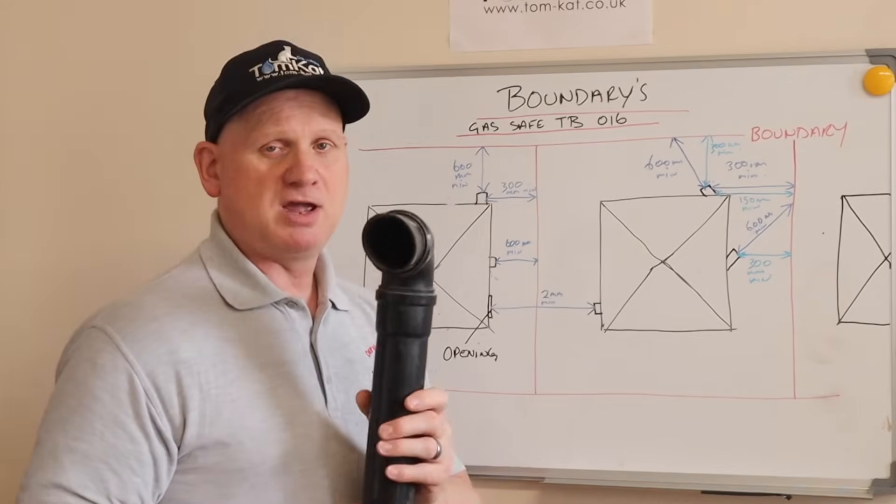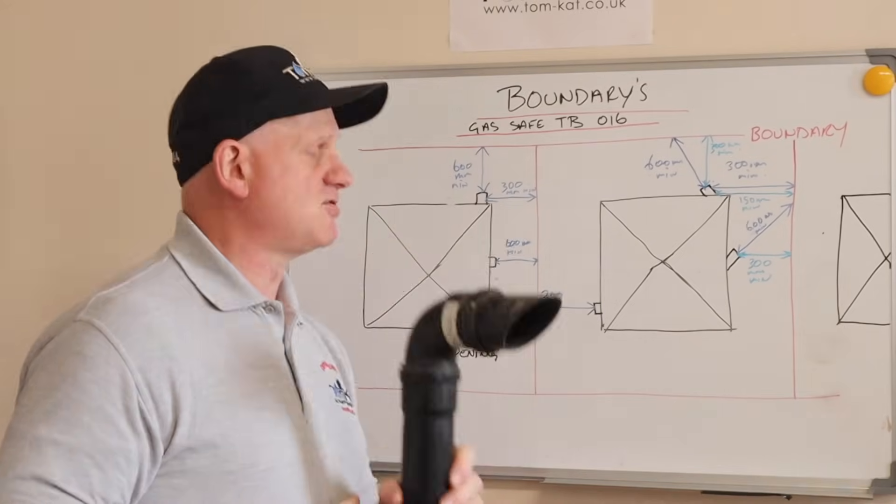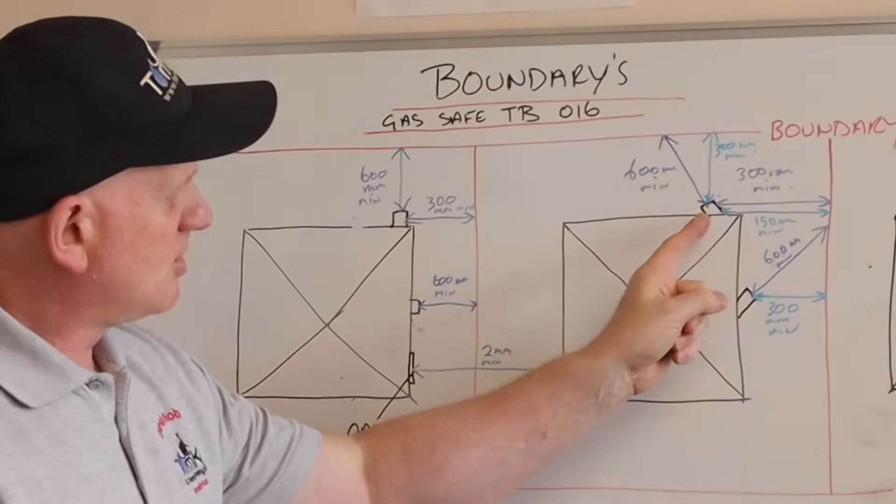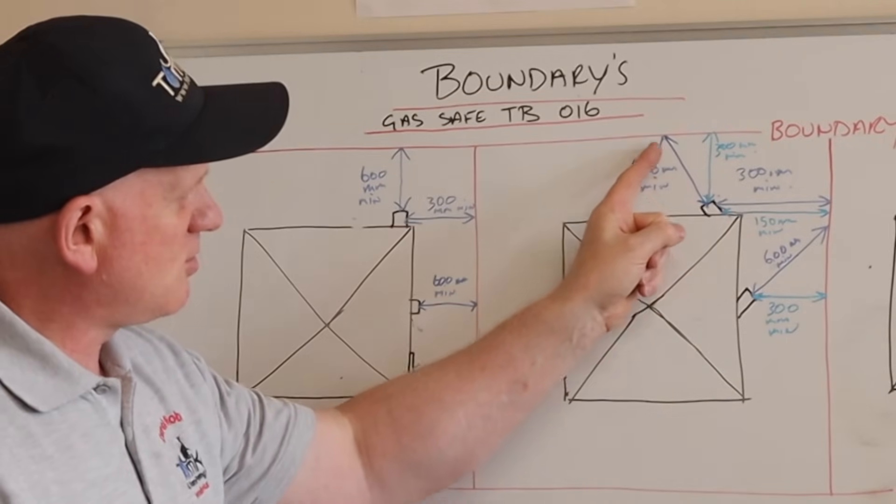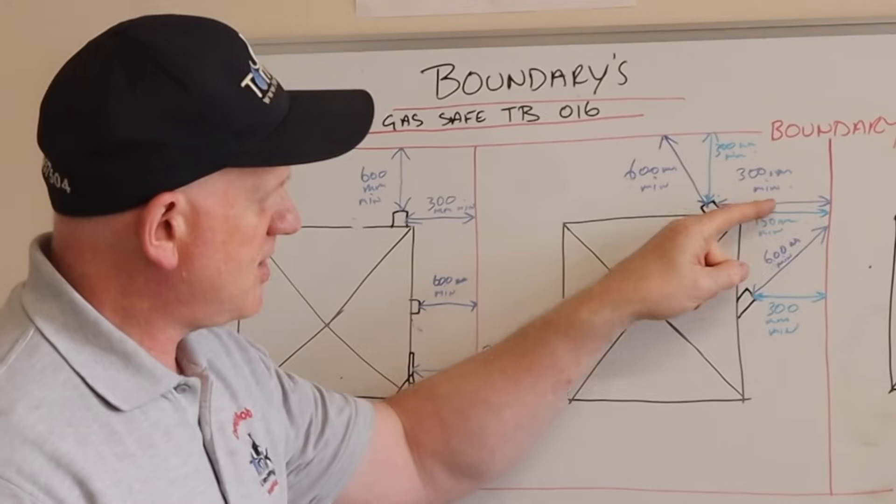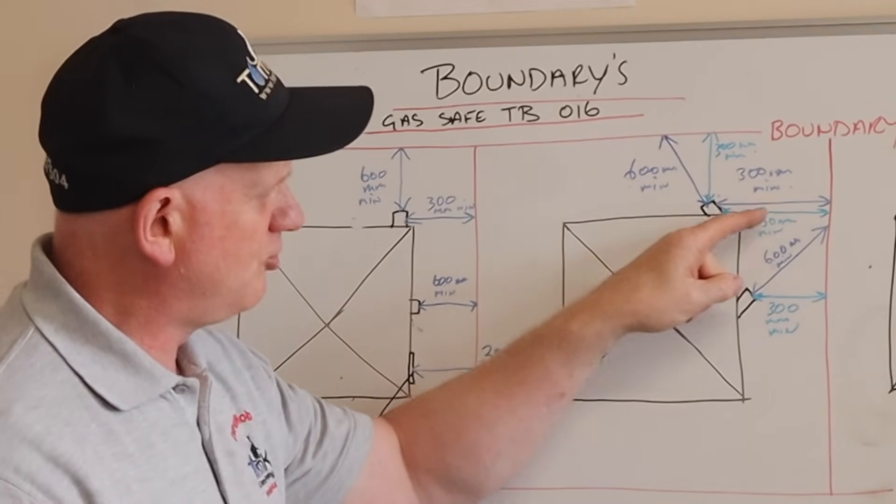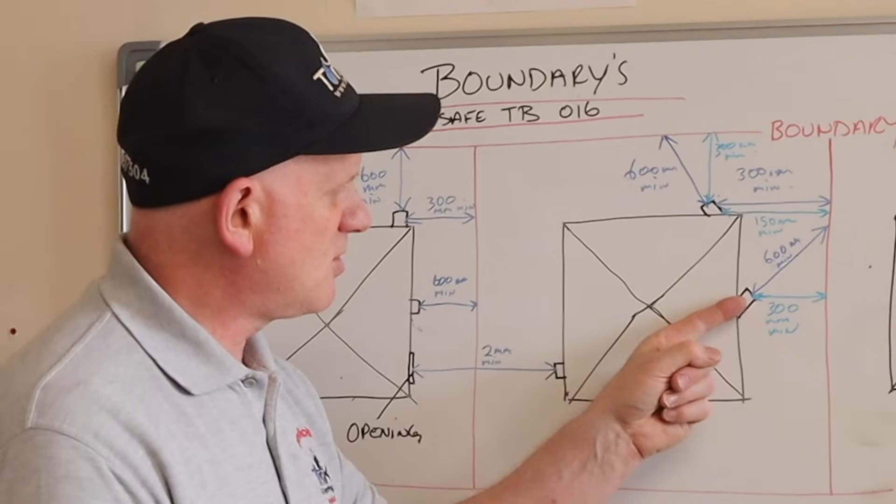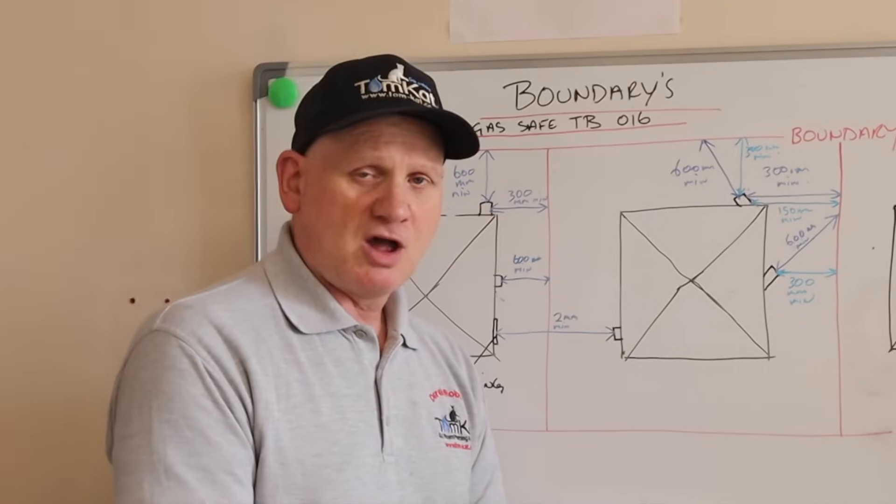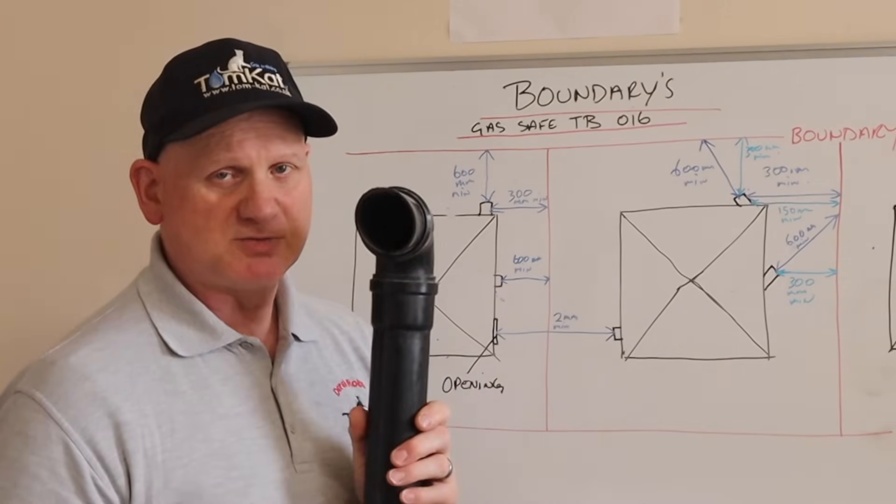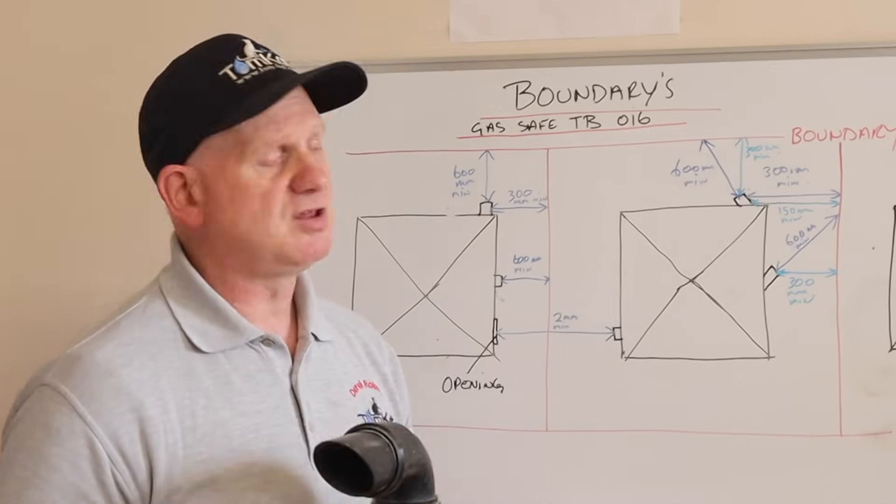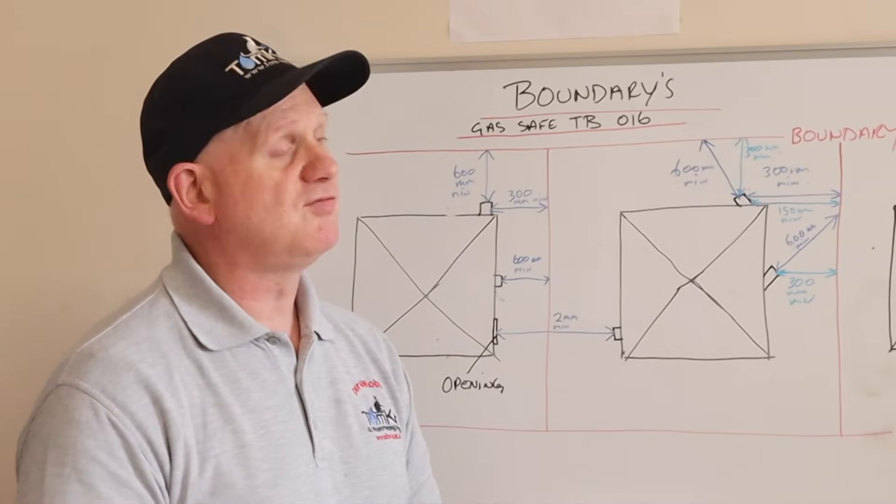Now, if we take our plume kit and we turn it 45 degrees, then we can reduce these measurements by half. So we've turned it 45 degrees, we've still got 600 there, that means we've only got 300 there. We've still got 300 here, but that means we've got 150mm. We've still got 600 here, but we've got 300 directly across. So, that is how this little plume management kit can alter your distances.